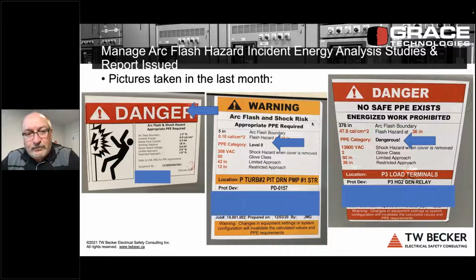So this is a systemic problem for the last 10 years of these studies, and there's a lot of these danger labels out there, no PPE exists, with a cutoff at 40 cals. The employer has been completely misinformed by the consultant doing the study that incident energy at 40 cals or greater will mean a high arc blast pressure.